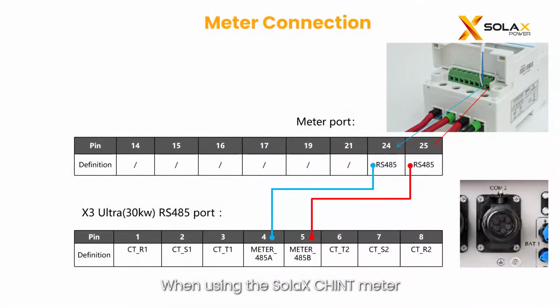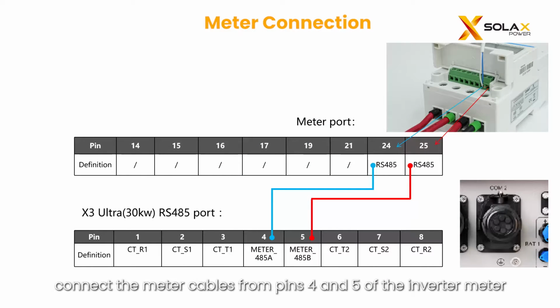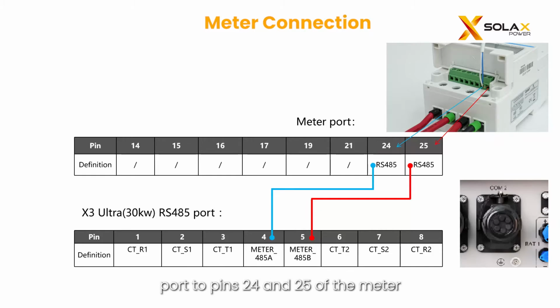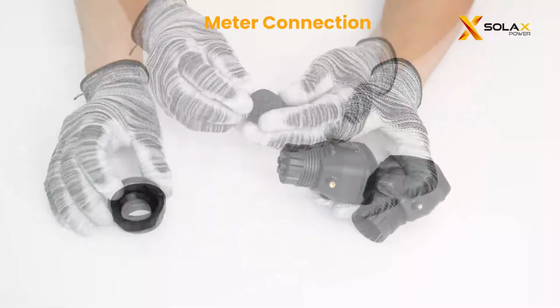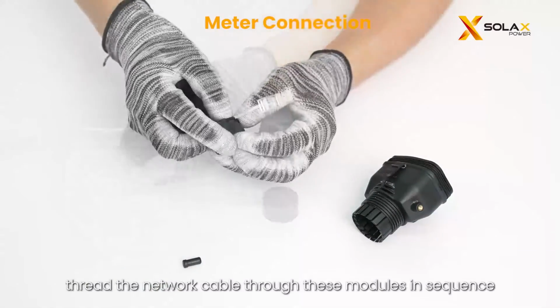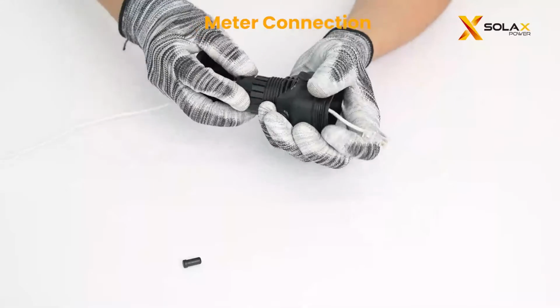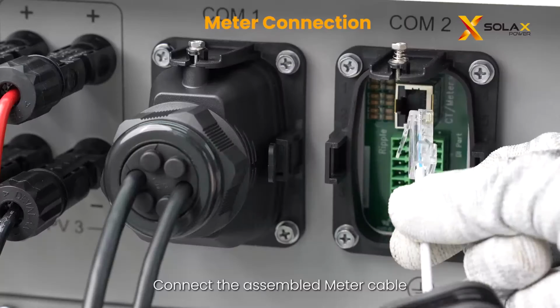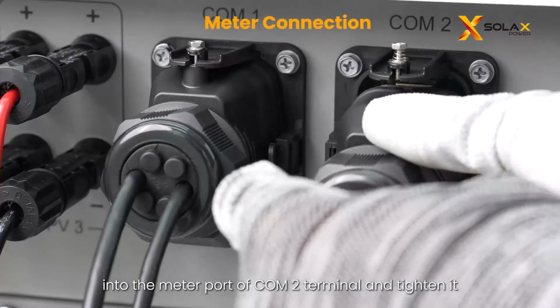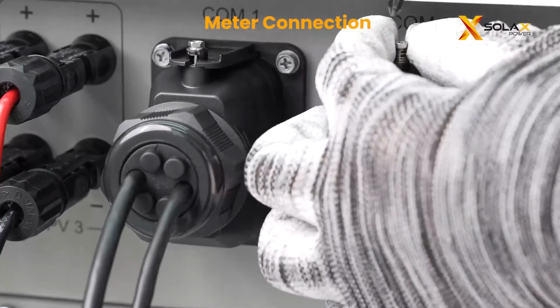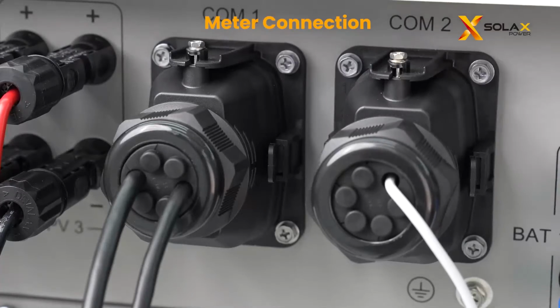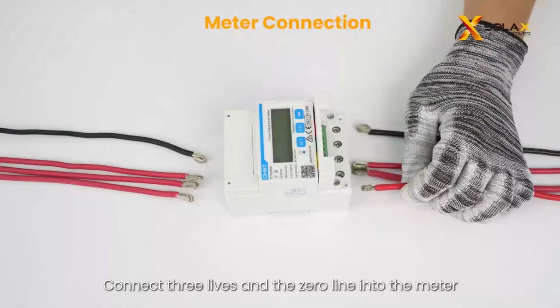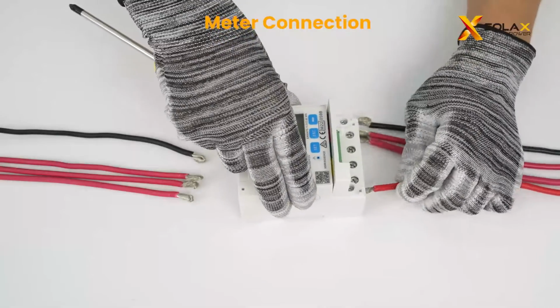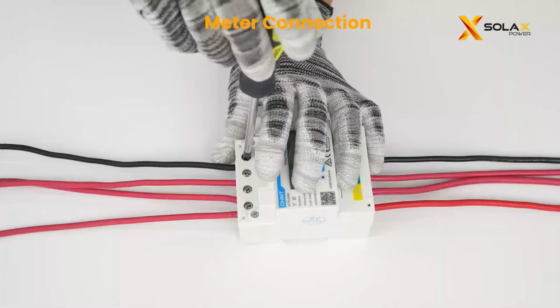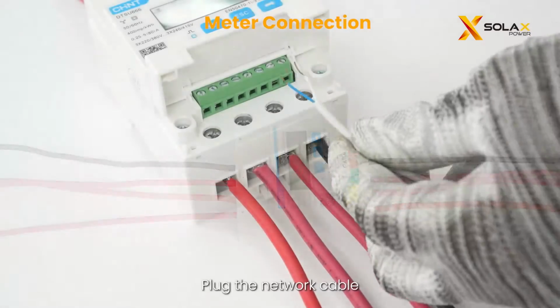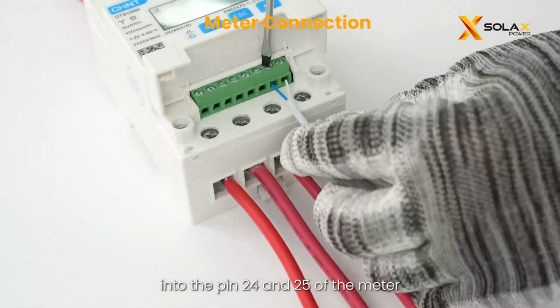When using the SolaX chint meter, connect the meter cables from pins 4 and 5 of the inverter meter port to pins 24 and 25 of the meter. Similarly, thread the network cable through these modules in sequence. Connect the assembled meter cable into the meter port of COM2 terminal and tighten it. Connect 3 lives and the 0 line into the meter. Plug the network cable into the pin 24 and 25 of the meter.